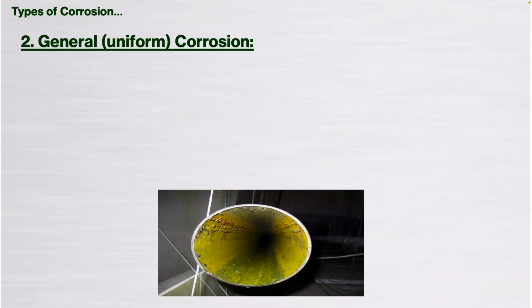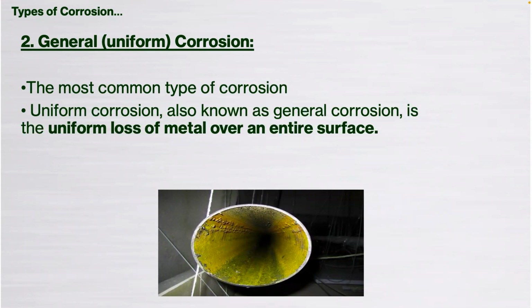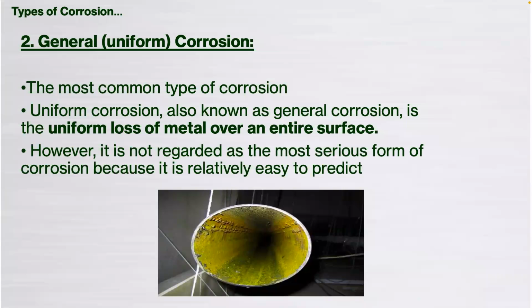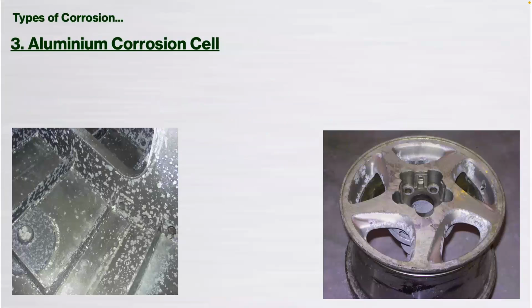General corrosion is pretty much what it says on the tin. It's the main surface area of a metal, and it's over the entire surface. Something that's very easy using corrosion coupons. We can actually measure the metal losses in a system. But it's not the most serious. As I say, it's fairly straightforward to predict and action.